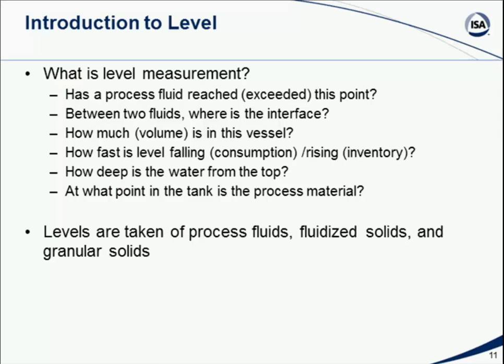We don't really care about the level in the tank. We want to know, do we have X number of gallons or cubic feet of something? Sometimes we care about level change, so it's not so much how much our level is now, but whether we've dropped below a certain critical point or how fast our level is dropping. Maybe that's an indication of a leakage condition, or maybe it's an indication, for example, that we are producing product, consuming what's in the storage tank at a certain level.